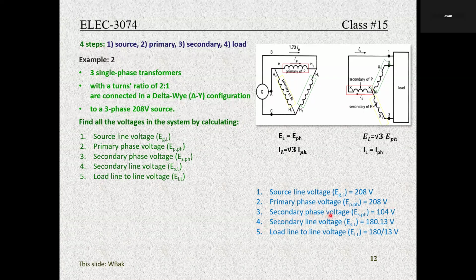Secondary phase voltage - how do we get the phase voltage? If we know the phase voltage on primary, and this coil is acting on this coil, and we know the turns ratio, which is 2 to 1, then this phase voltage - that's all we're concentrating on right now - follows that ratio. If this one is 208, this one is going to be 104. So here's 104 across this coil, 104 across this coil, 104 across this coil. So we have the secondary phase voltage, 104.